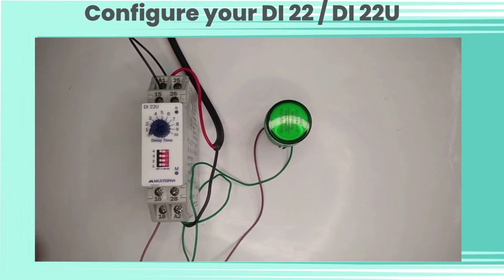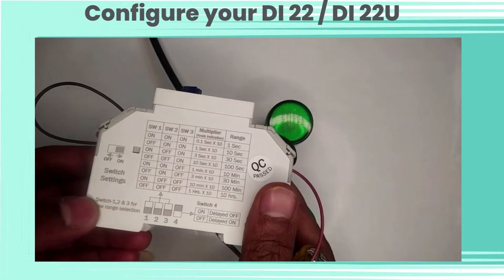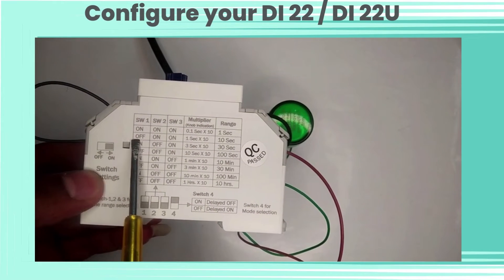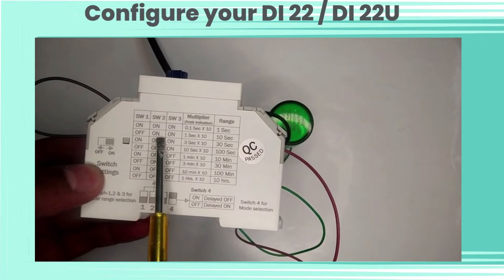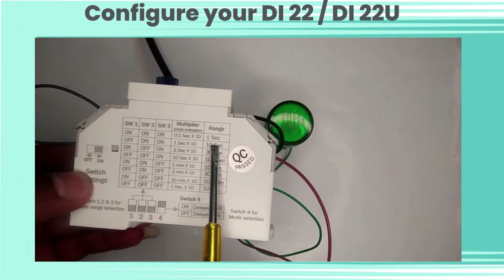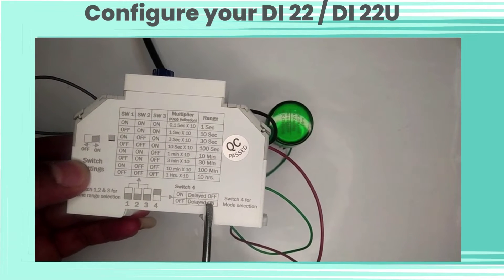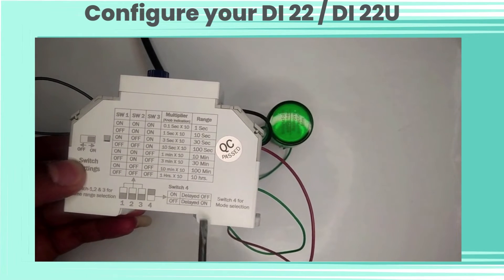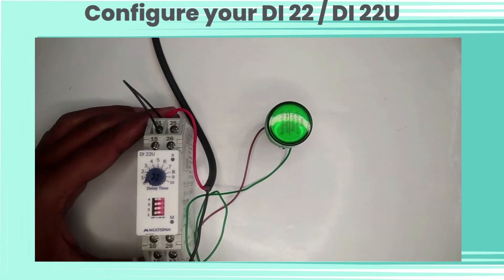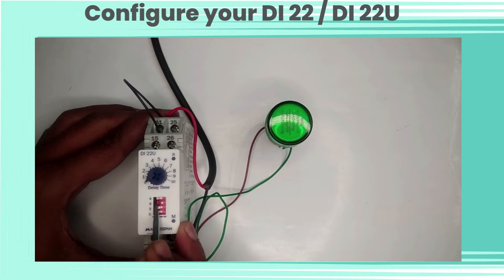Now let's configure the DI22U. For various time selections, we have three switches available. Here we are going to select a switch for 10-second timing. For 10-second switch selection, we have to change the status according to our switch chart. From switch 4, we can change the switch condition for delayed off or delayed on.